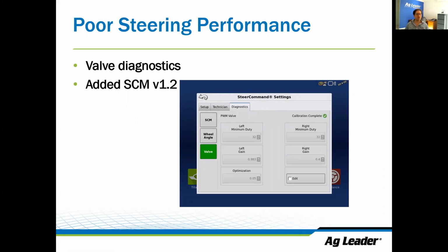Also added in the latest firmware is valve diagnostics, showing us our duty cycles and gain. Again, this is more from a diagnostic perspective rather than a troubleshooting solution perspective. Looking at our gain values, we can see whether our right and left are the same, to see whether we might have a problem with some physical component in the valve.